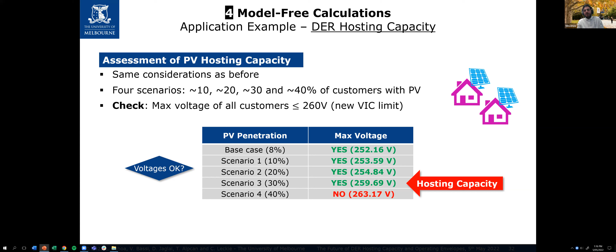Again, the check is to see if the maximum voltage of all customers is within statutory limit. We want to check if voltages are okay, and the results show that up to 30% of PV penetration in our low voltage network, we do not observe voltages beyond statutory limits. For the base case, scenario 1, 2, and 3, up to 30%, voltages are within statutory limits, whereas when we increase penetration a bit over 30%, voltages go beyond statutory limits.